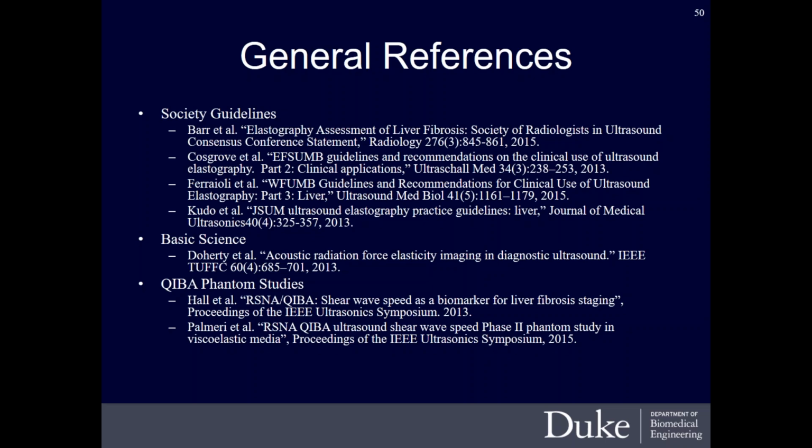And MRE was chosen as a good comparative modality because it's such a narrow band, discrete frequency that it hones in and is not affected by that slope or gradient of speeds at adjacent frequency bands. And luckily the MRE community has been very collaborative in this regard. Plus it would also help down the road clinically that an MRE system should hopefully agree with an ultrasound elasticity system, though right now, as I mentioned, the MRE systems measure closer to 60 hertz, whereas the ultrasound systems are up at a higher 140 hertz.